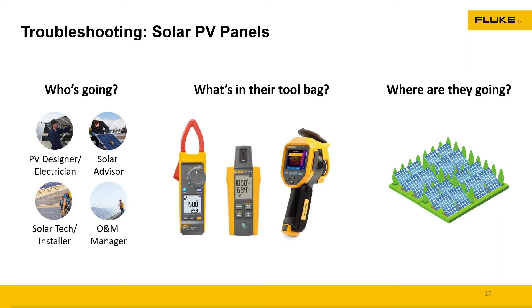They're going to need a meter to measure voltage and current coming off the panels. They need an irradiance meter, because based on the panel manufacturer's data plate, a certain amount of irradiance should give a certain amount of voltage and current off that panel. At times they may also need a thermal imager to look for cracks in the system, and you can see if a bypass diode has failed just by using a thermal imager.